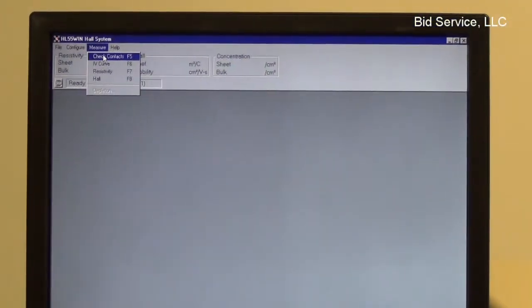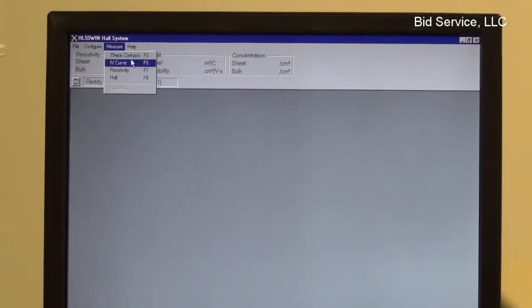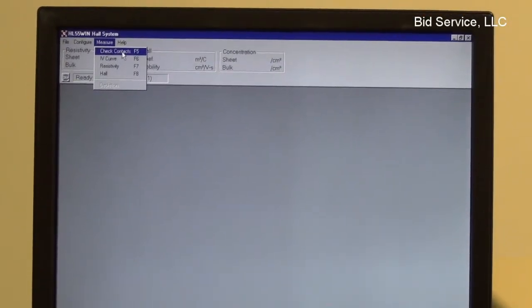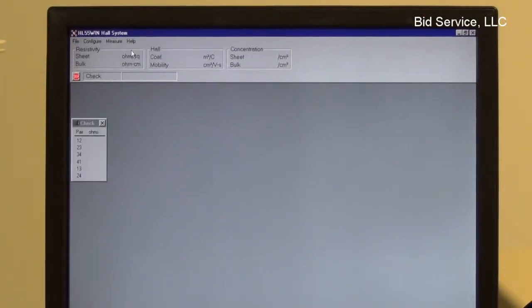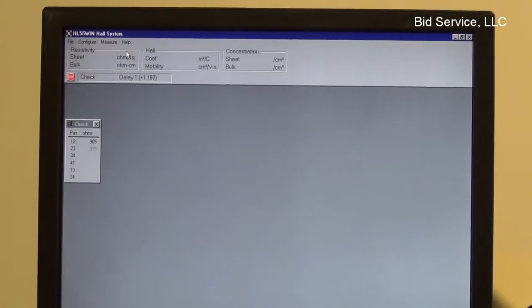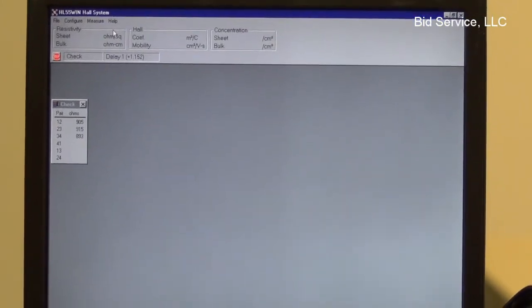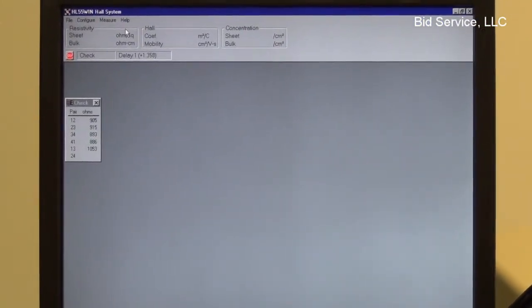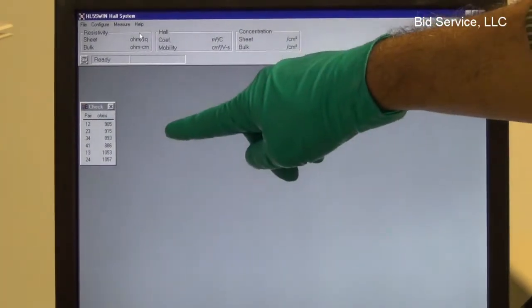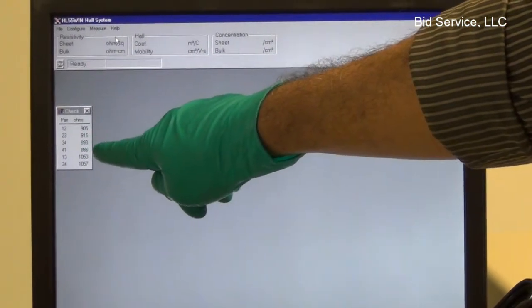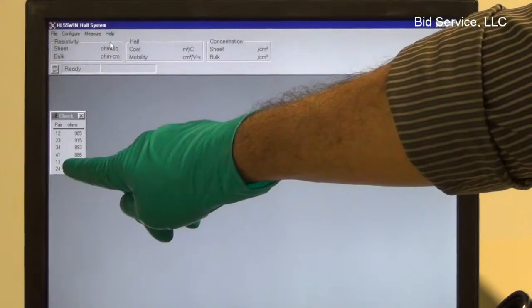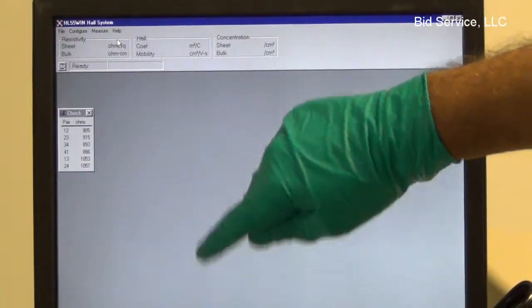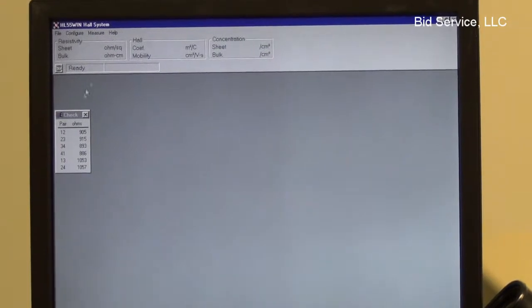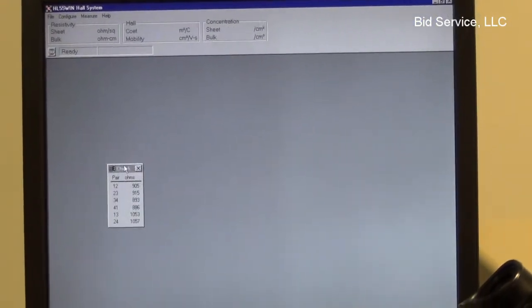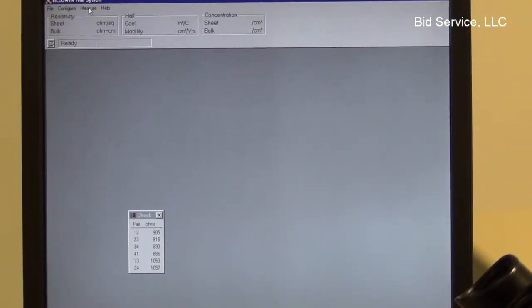So now I'm going to do the measurement. The first thing I would do is checking the contacts. Click on the check contacts. So the values are measured between the probes 1 and 2, 2 and 3, 3 and 4, likewise until 2 and 4, all the values are displayed. And the window can be moved to a convenient location.